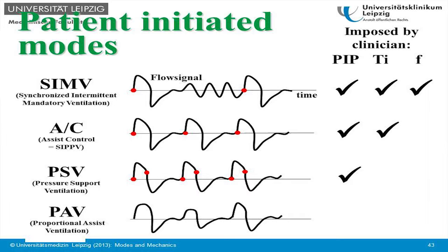In assist control ventilation, the clinician sets peak inspiratory pressure and inspiratory time, while the patient is in control of the frequency. And in pressure support ventilation, the patient also gets control about inspiratory time. The only thing which is set by the clinician is the peak inspiratory pressure. And in proportional assisted ventilation, everything is controlled by the patient.